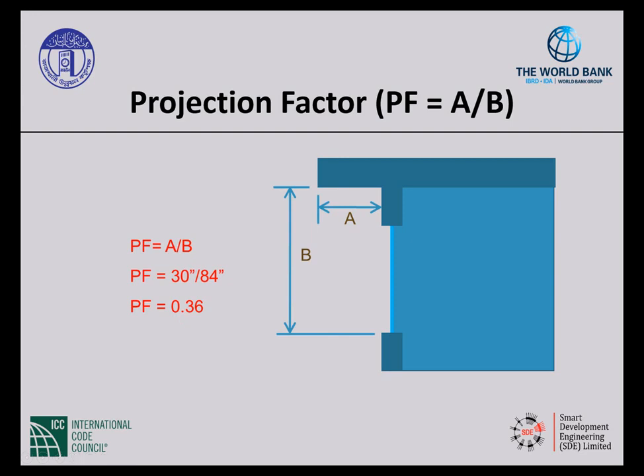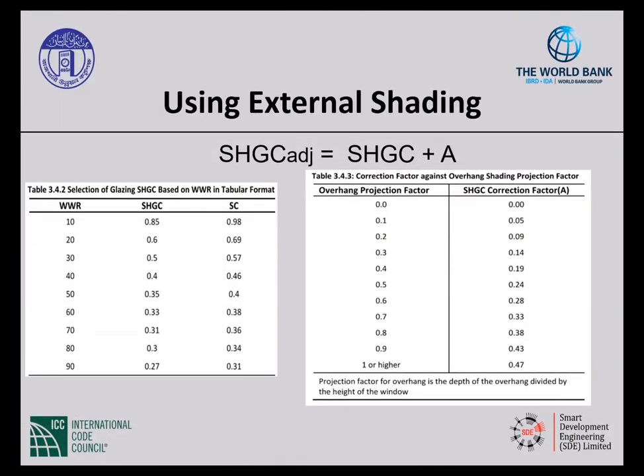So when I go back to those tables, I can look at this table here on the right for a projection and okay, I'm 0.36. Well, I have 0.3 and 0.4, so I'm going to round up. So I'm going to go to 0.4 projection factor. And if I have a 0.4 projection factor, I can use my solar heat gain correction factor of 0.19.